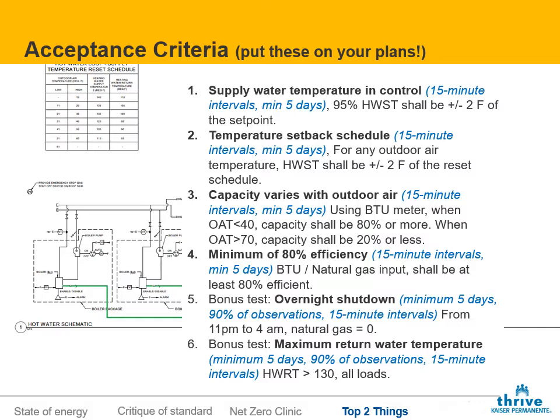Bonus test number 1 is that if this is a medical office building or a clinical building, then from 11 p.m. to 4 a.m., we should see the system shut off, and that should show up in the natural gas numbers. And then the second bonus test is that if this system is a condensing boiler, which it's very popular to specify, then the hot water return temperature should always be 130 degrees or below for 90% of observations.